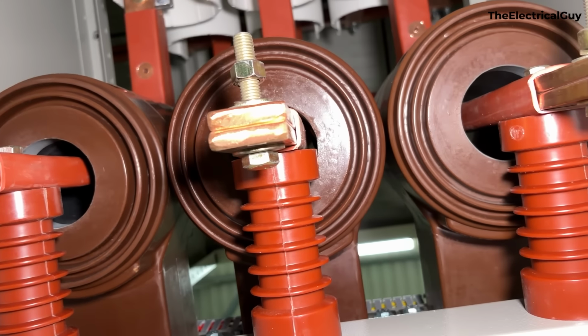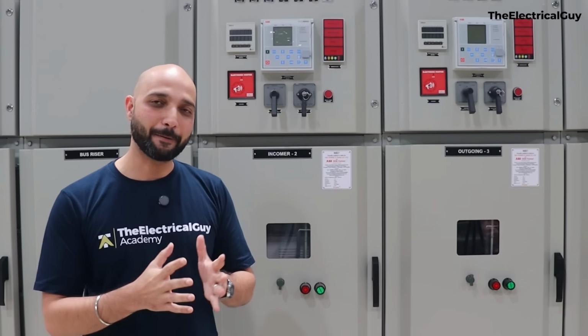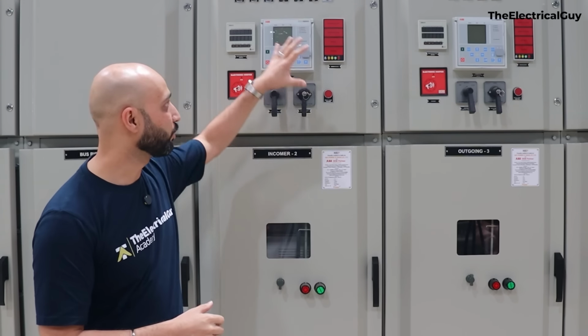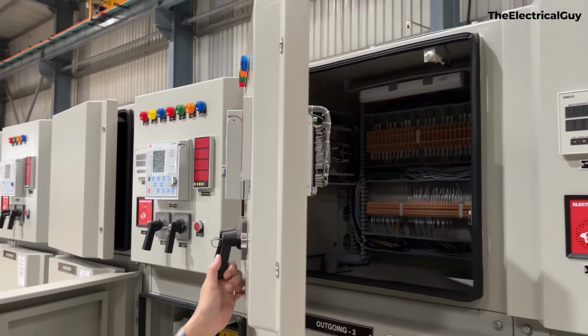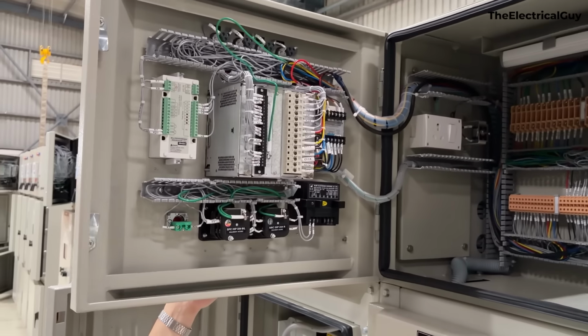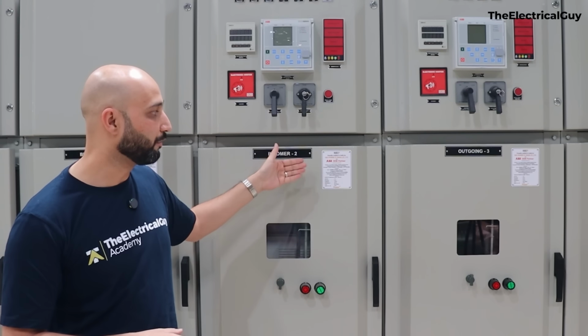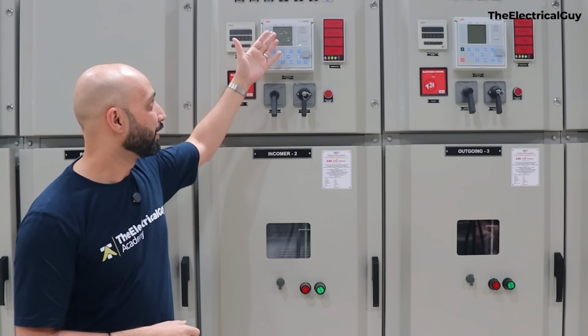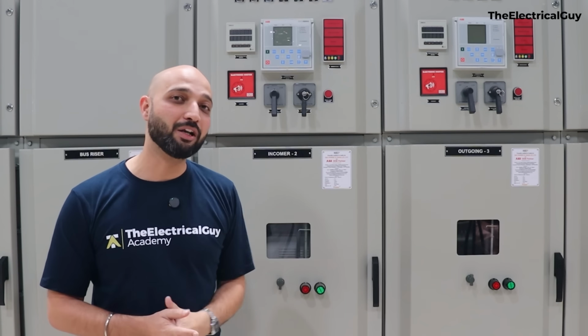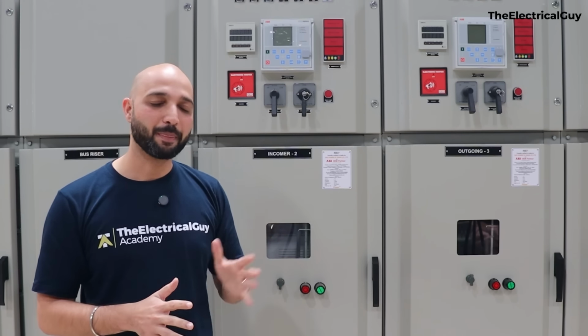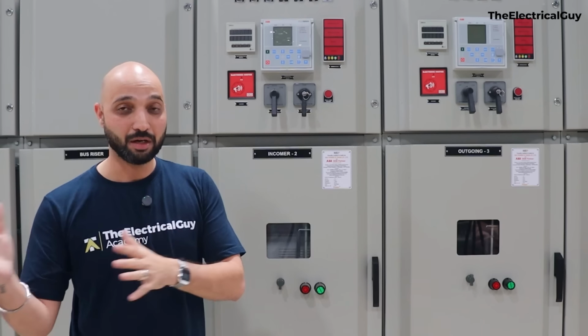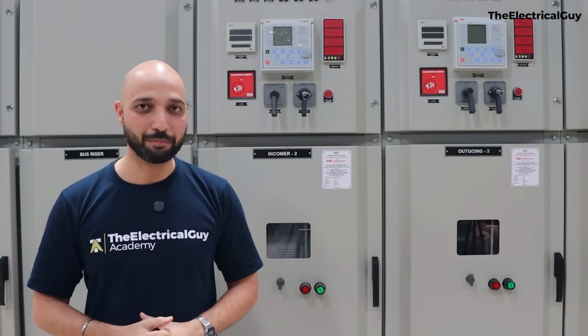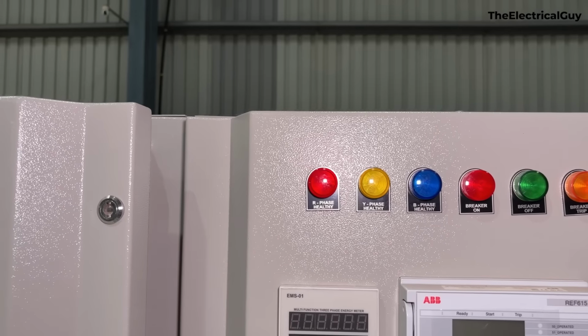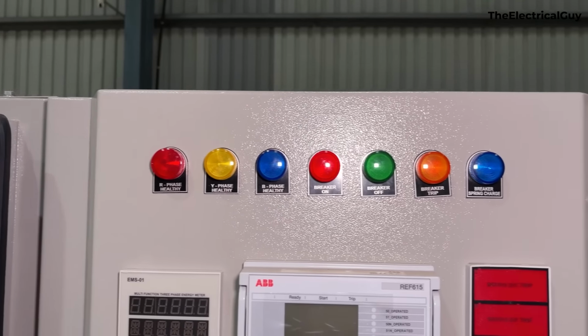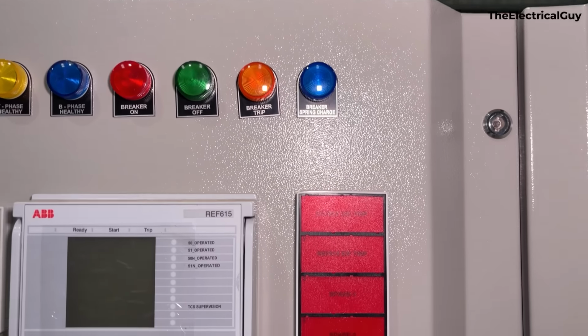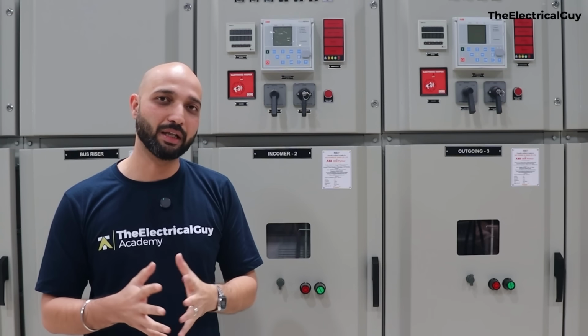So from there we are going back to the current transformer, which you can see at the back of the panel. The current transformer is needed so that we can step down the current, because the meters and all that we have on the low voltage side cannot accept the current that is coming inside the panel. So for example, this is incomer 2 and we have 1250 ampere as the current. So the relays, the meters are not meant to accept that current. So we must step it down, and for that we are using current transformer, and voltage transformer as well for the same purpose. The input of that voltage and current transformer will go inside the relays, inside the panel meters, that will help us in measuring and protecting our system.